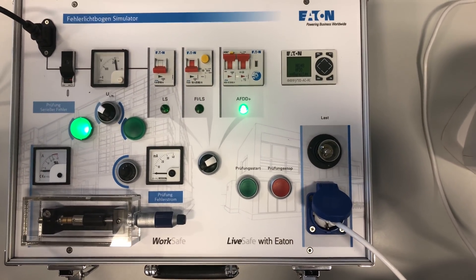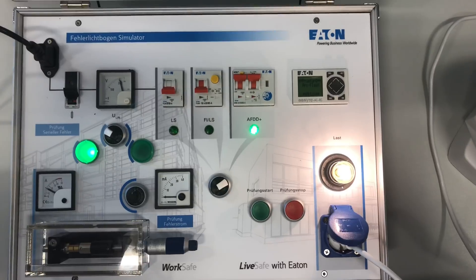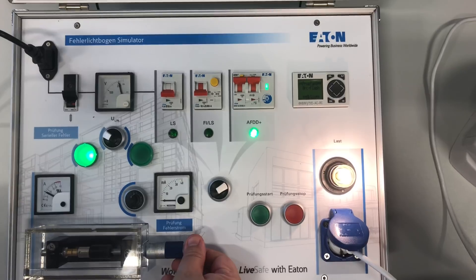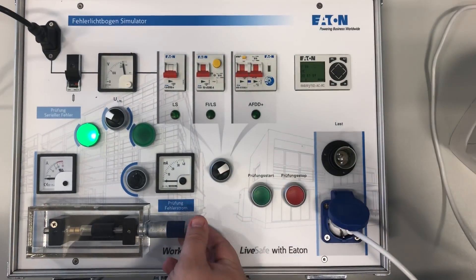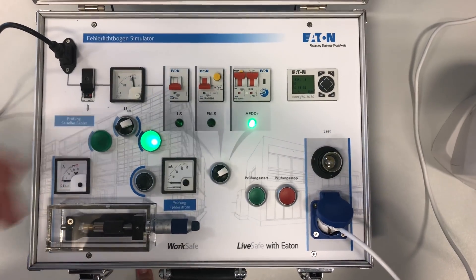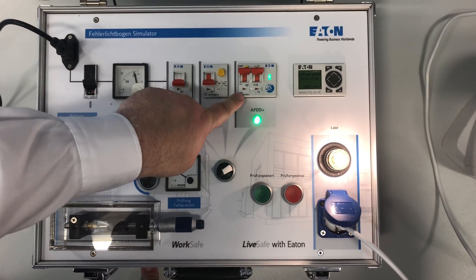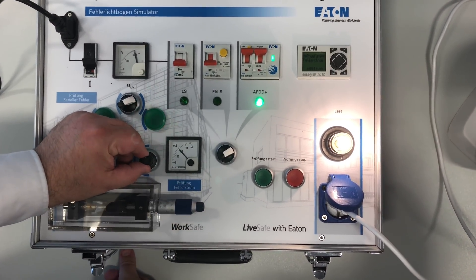We'll flick it over to AFDD. AFDD's on — press start again. Now screw it out. Seven and a half amps. Instantaneous — instantaneous. For the next additional test, we're now going to do the RCD component of the AFDD. Start it — it's now on AFDD. You can see the flags, and now we're just going to twist it up, go up to 20 milliamps. There we go — trips. We've just proven the devices.